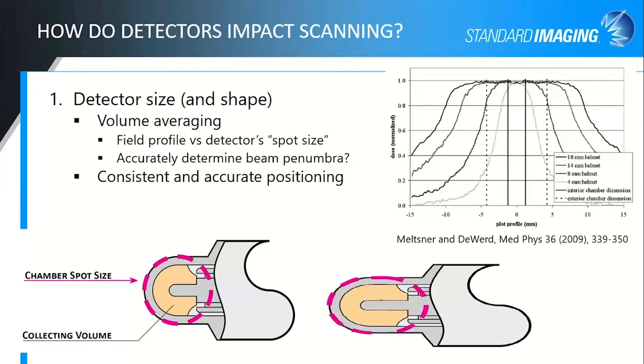I know that's what we're trying to measure with the scanning, but to have some understanding of it relative to your detector's spot size. And what I mean by spot size is this full dimension that it's integrating over. So we're including in our definition of spot size the wall of the chamber as well as the actively collecting air volume, in this case for the ionization chamber. But this is the active region that's affecting your measurement.